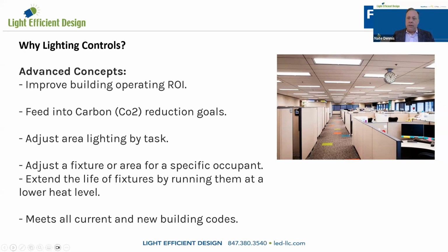When you're running that fixture at a lower light level, you're still creating less heat, even if it's an LED application. So for people worried about long-term longevity, this is something you can address with a lighting control system.